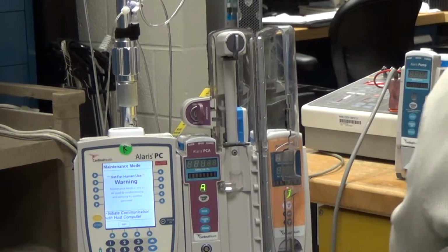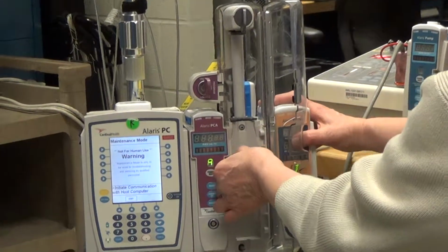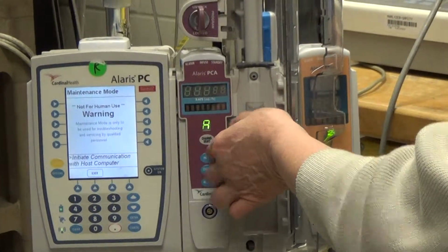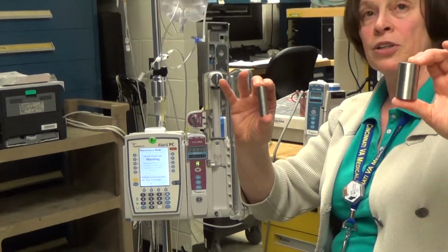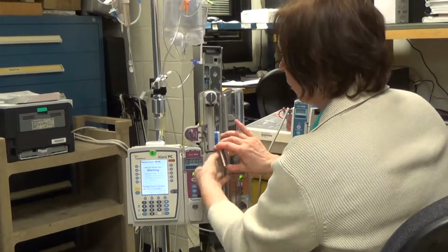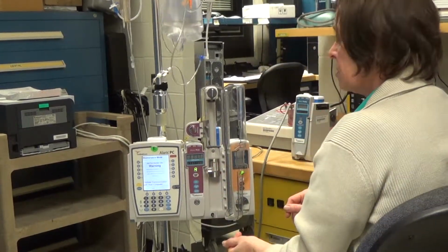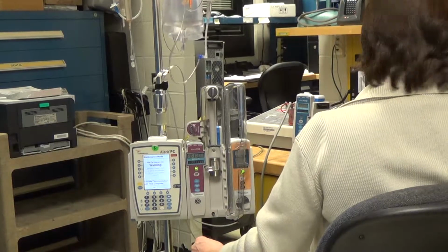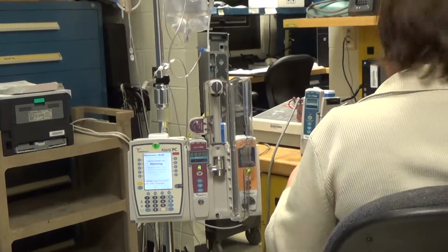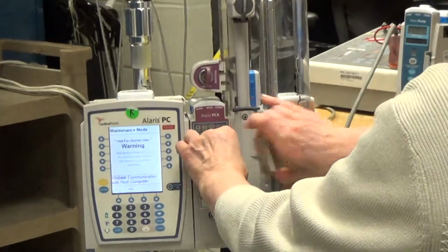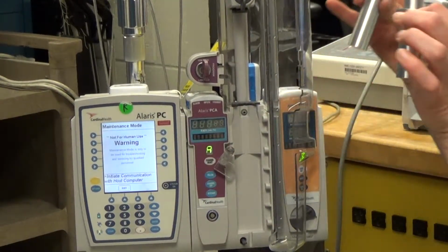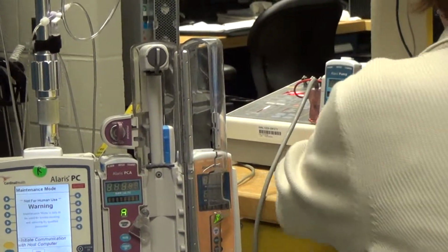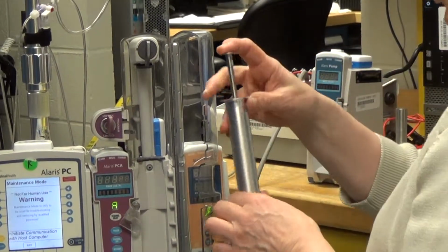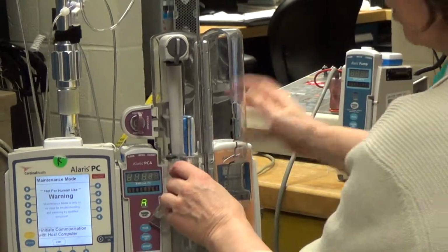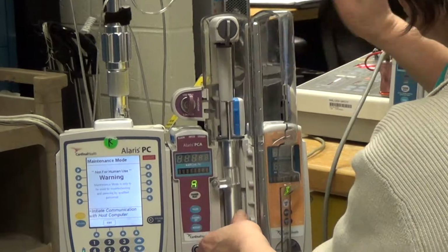We are now getting to the point where we need to check and make sure that the barrel can correctly detect the size of the syringe. For that purpose, we have different size cylinders. They are inserted like this, and we get the measurements and connection on the computer. There are different sizes and height, lengths. And then we come to the point where we can calibrate and adjust for different heights.